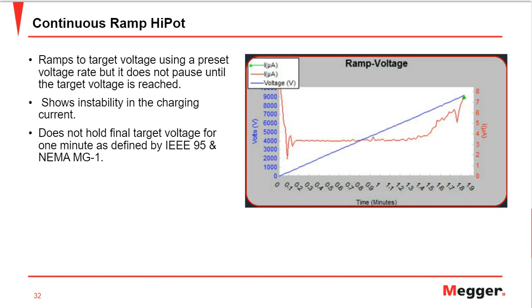The increase in the current initially is due to the capacitive current, and as the test progresses, if the insulation is not good, we'll see an increase in the test current or changes in the graph. So the capacitive inrush current rapidly drops to 0, which we've seen from the total currents, and the remaining current is measured. What is measured is mainly due to the surface currents and the conduction leakage currents.